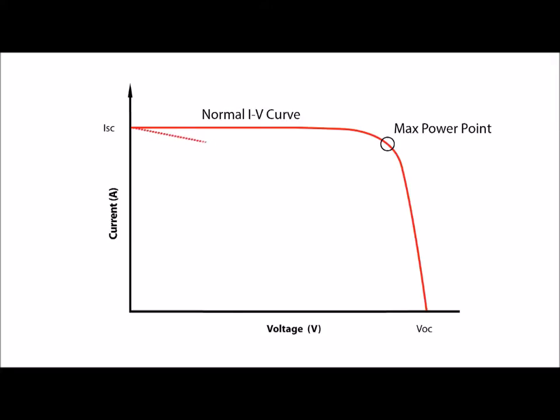For instance, the slope at the top of the curve will reveal possible shunt losses and the slope at the right side of the curve will indicate the amount of series loss. Notches in the curve indicate mismatch which can be caused by shading or other effects.